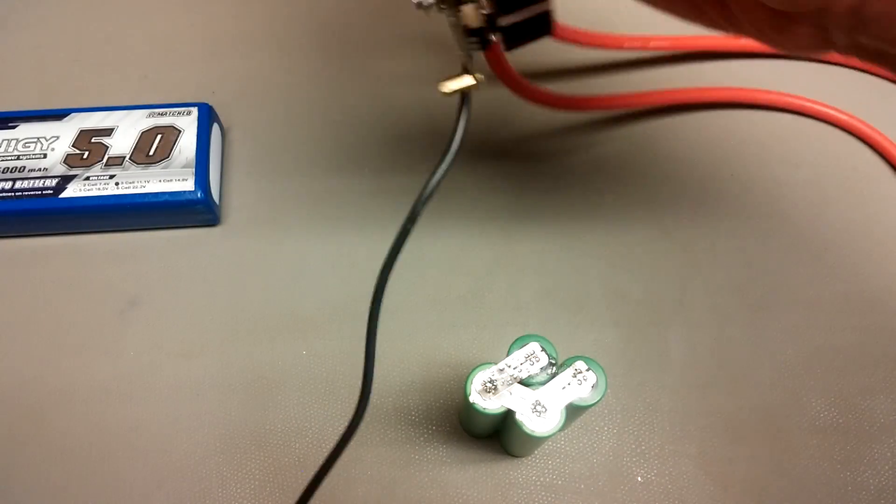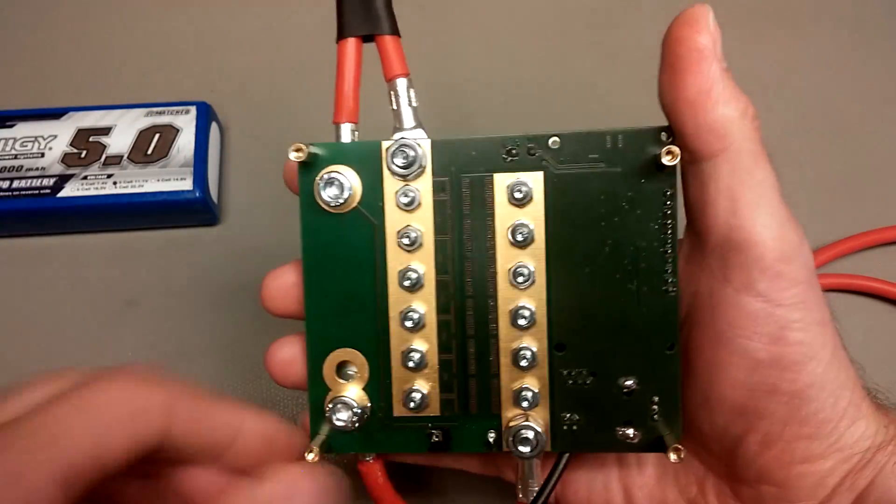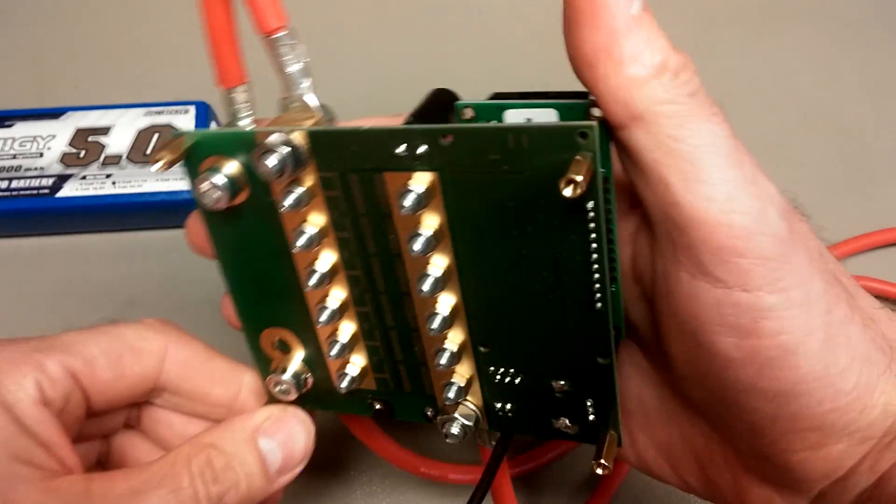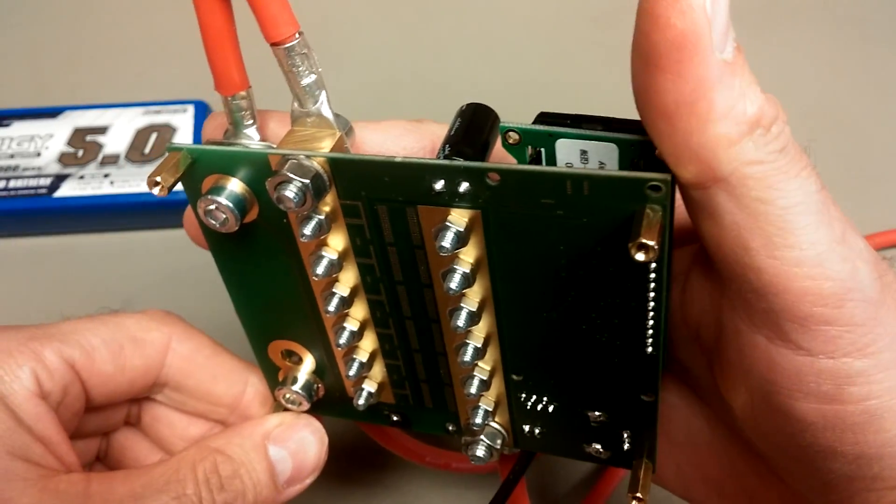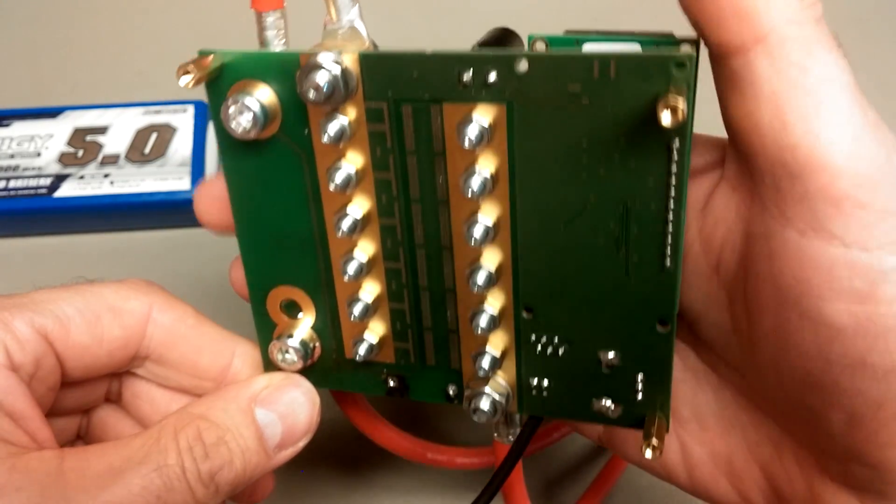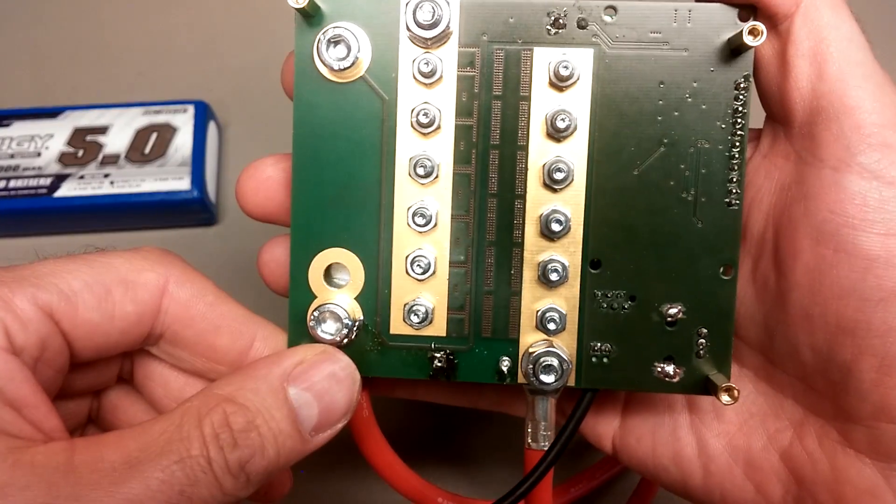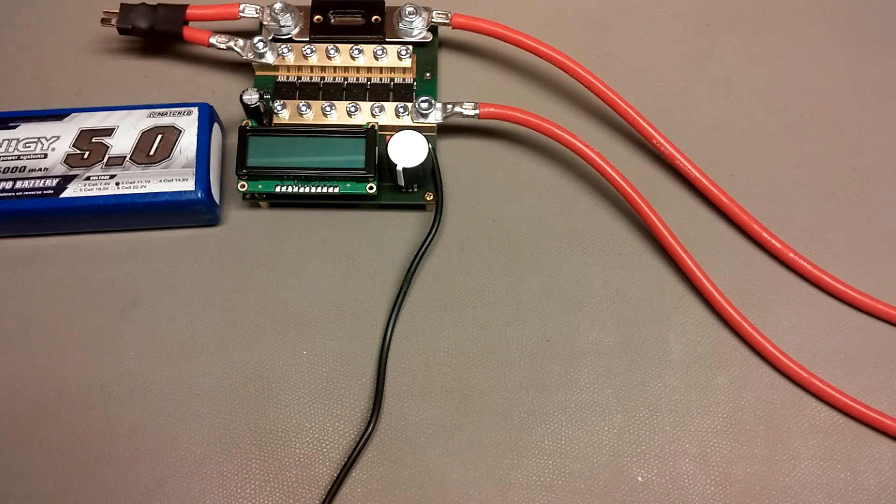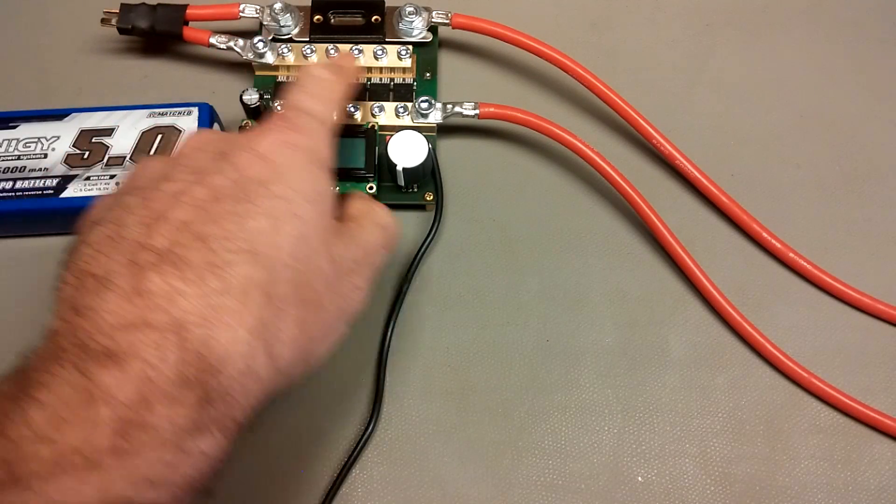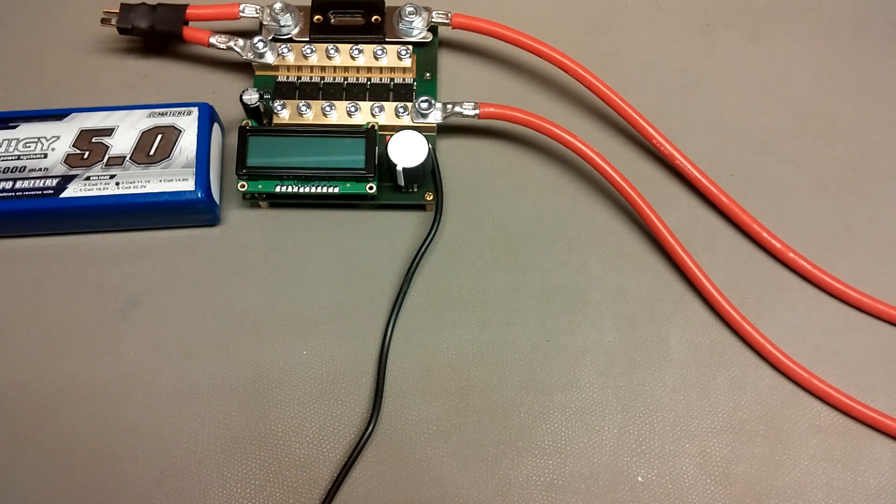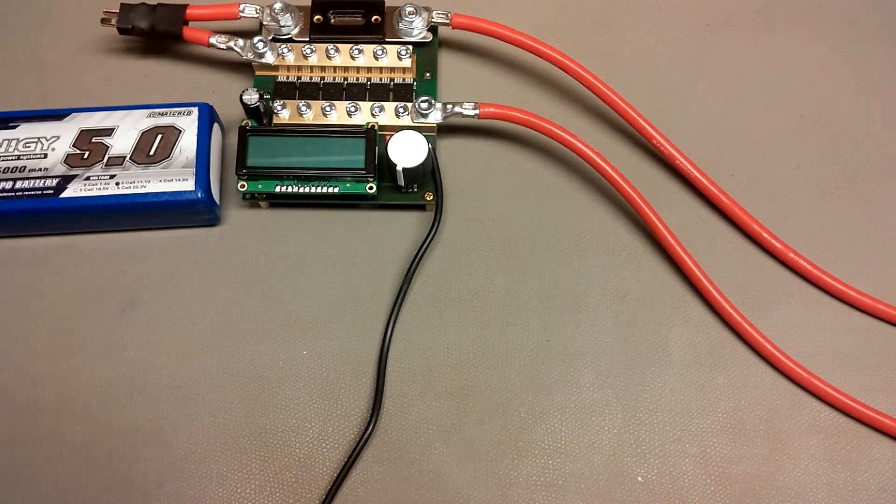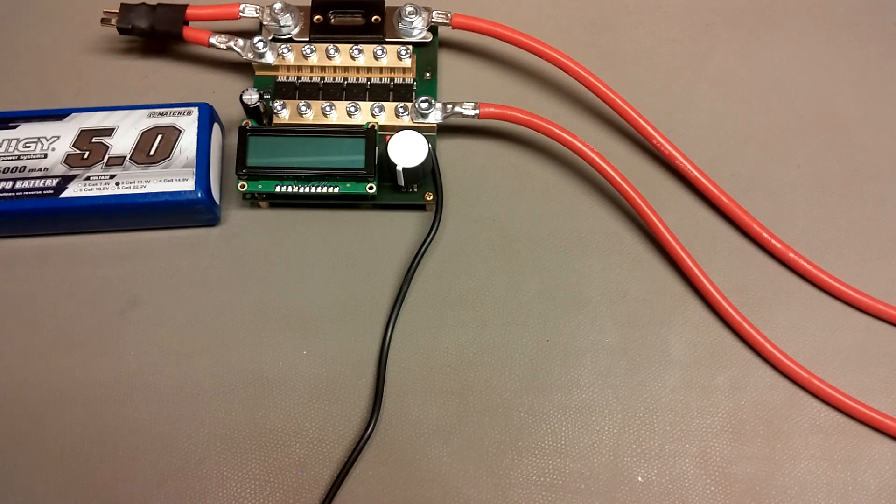Second thing is that I tried to simplify the mechanical construction and tried what happens if I remove the bottom side brass bars and replace them by nuts and washers. And the result is promising because the ohmic resistance of this signal path is even lower now. It's now 120 microohms instead of 140.